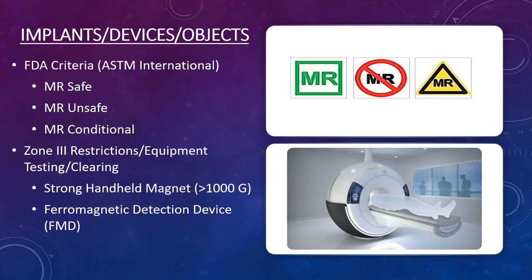The FDA has a criteria of MRI safety labels. The green square means MR Safe — the device has absolutely no metal. An MR Conditional label means the device can go into the magnetic field but has specific conditions for doing so safely. The red circle with a crossbar is MR Unsafe — these devices will pose severe risk in the MRI field.